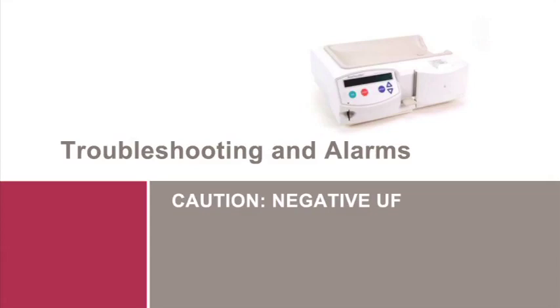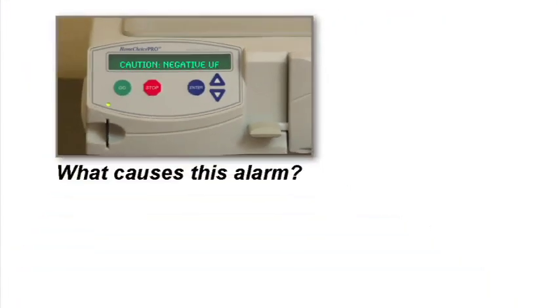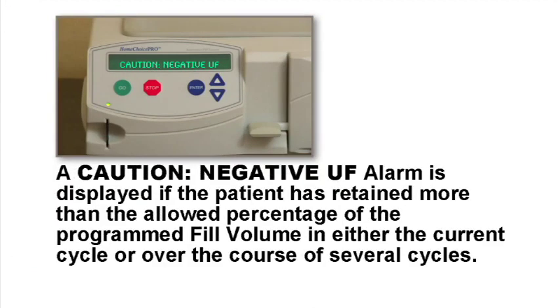Troubleshooting and alarms: Caution Negative UF. What causes this alarm? There are several potential causes for the negative UF alarm to sound. A caution negative UF alarm is displayed if the patient has retained more than the allowed percentage of the programmed fill volume in either the current cycle or over the course of several cycles.